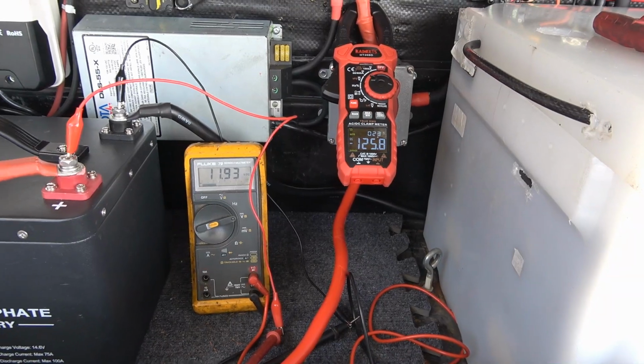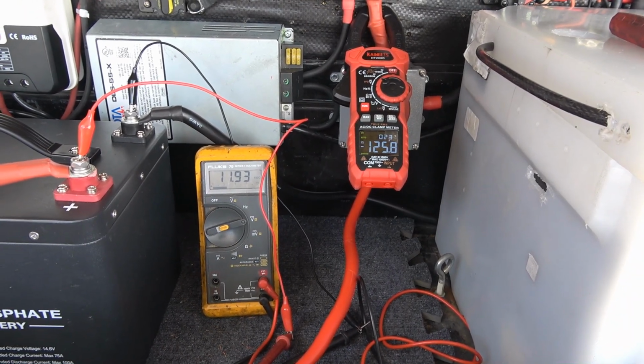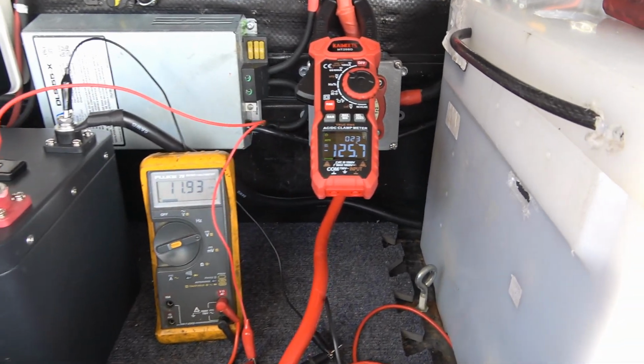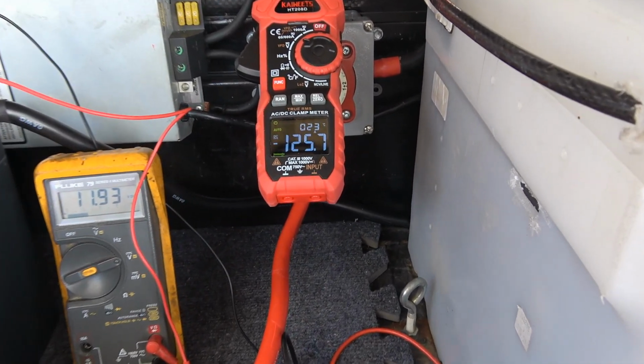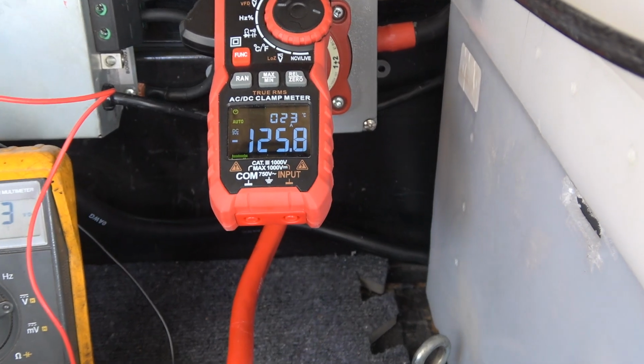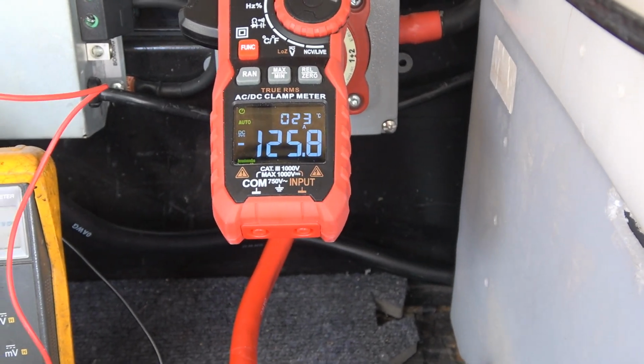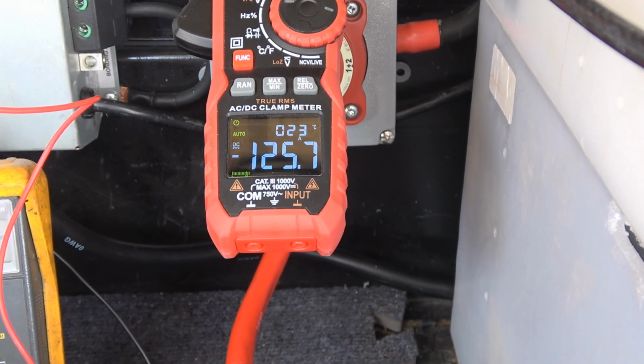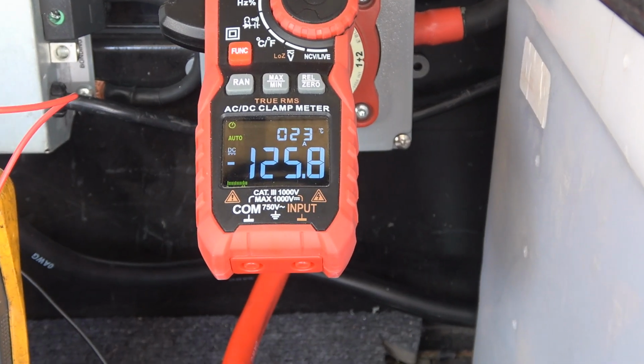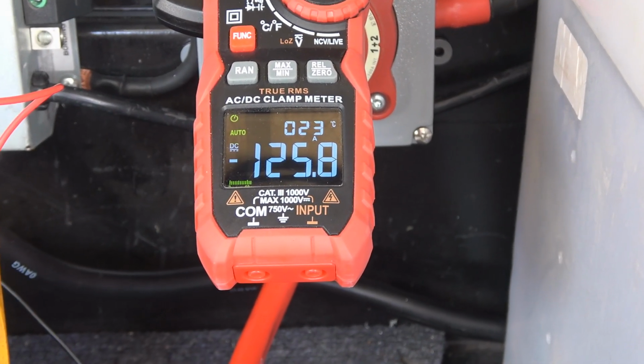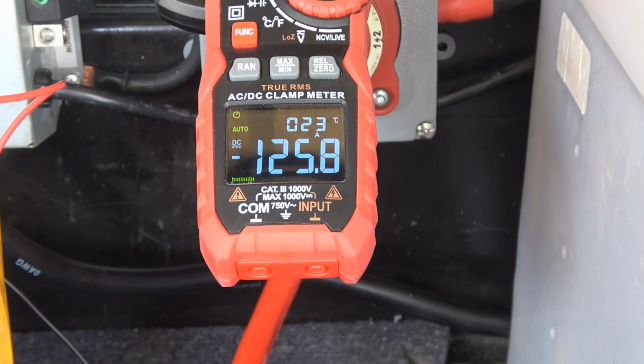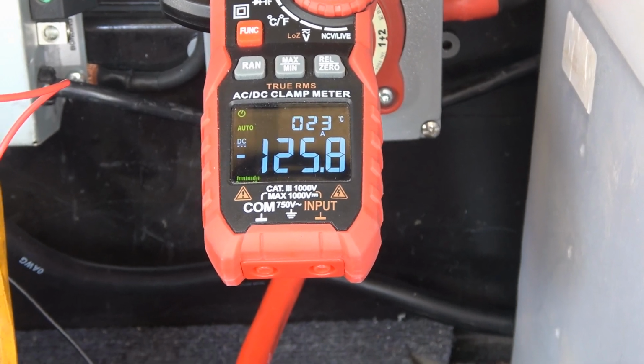Okay, just to double check that discharge, they actually sent me 2 of their batteries, so I've got the second one hooked up, and it's been running several minutes at 125 amps. So obviously that 100 amp max is not disconnecting the battery, which allows the cells to run at a higher rate than they're set for.